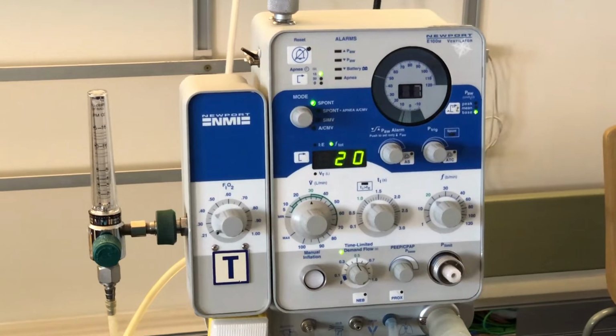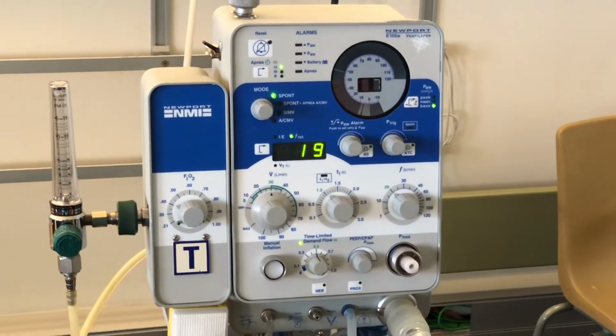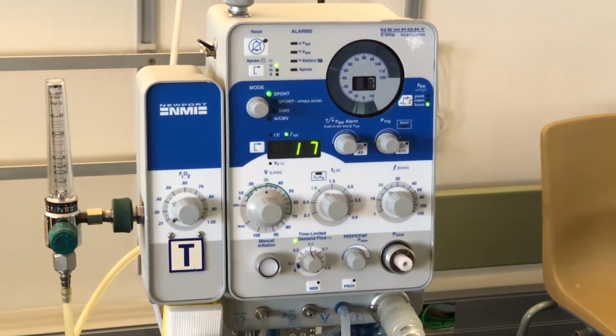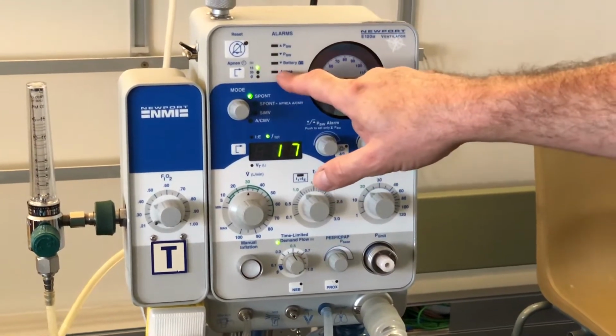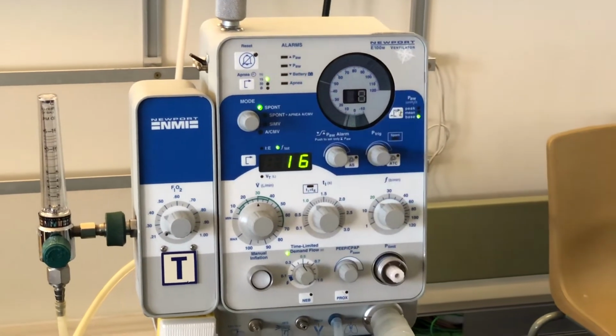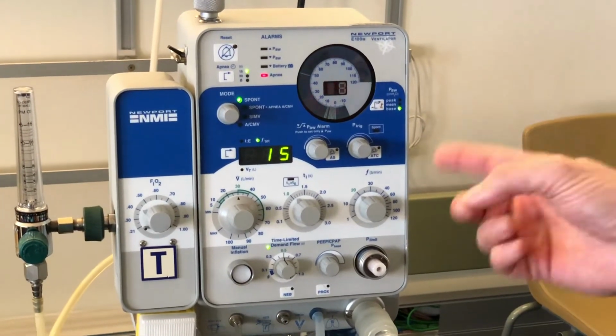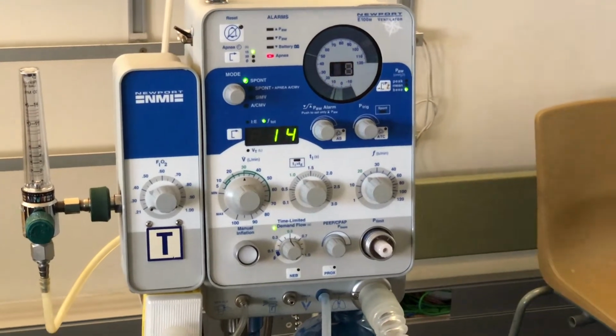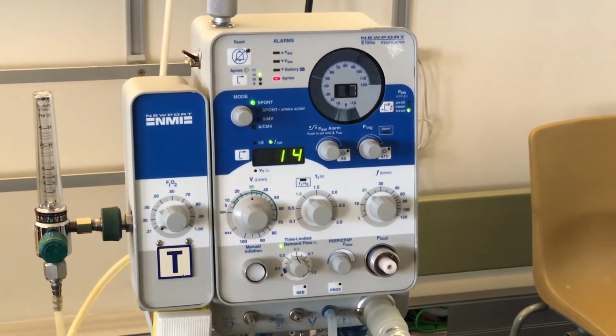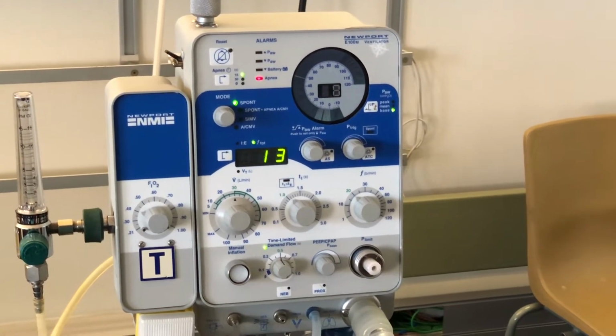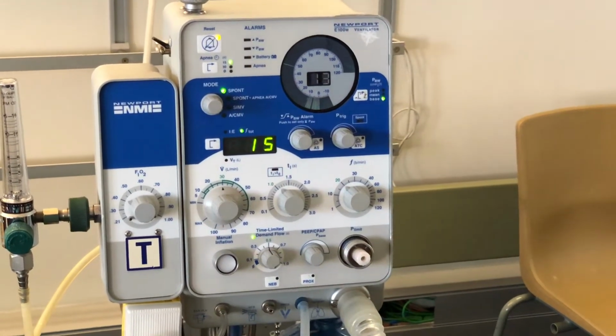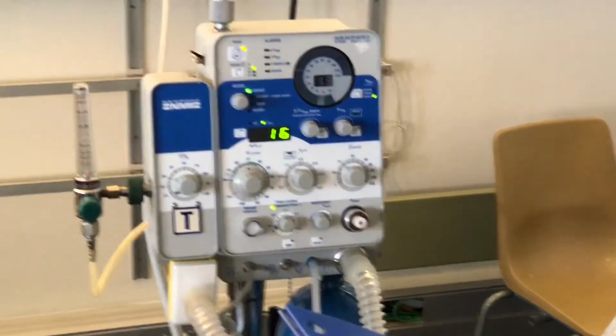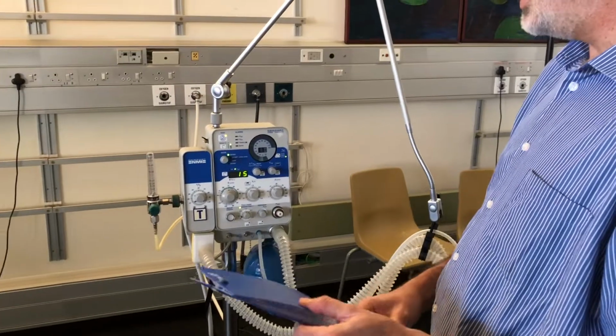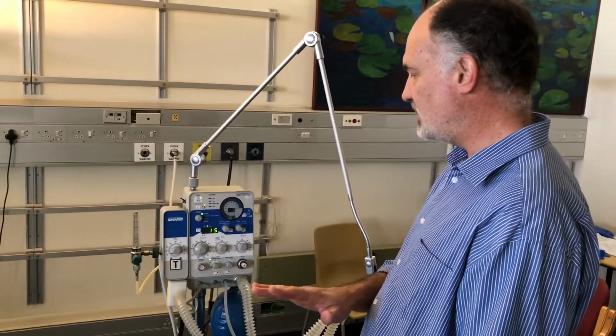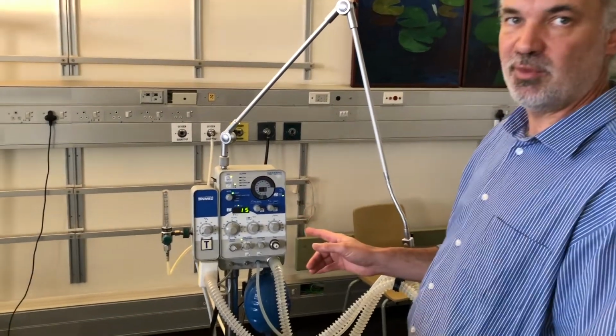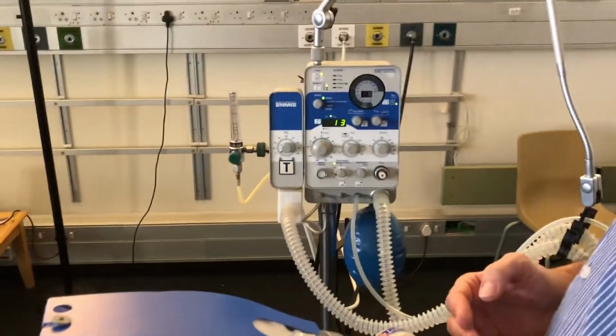I'm going to go now, though, to the spontaneous mode. So this is spontaneous mode without apnea backup. And you'll see the difference now is the machine detects that there's an apnea. The patient hasn't taken a breath for 15 seconds, but the machine just alarms. It doesn't initiate any backup ventilation. If I start to breathe now, you can see the light stops flashing, and I can go and clear the alarm, and the machine will continue to allow the patient to breathe spontaneously. But again, if there are no patient efforts detected, then the machine will just alarm for apnea. It won't commence any automatic ventilation.